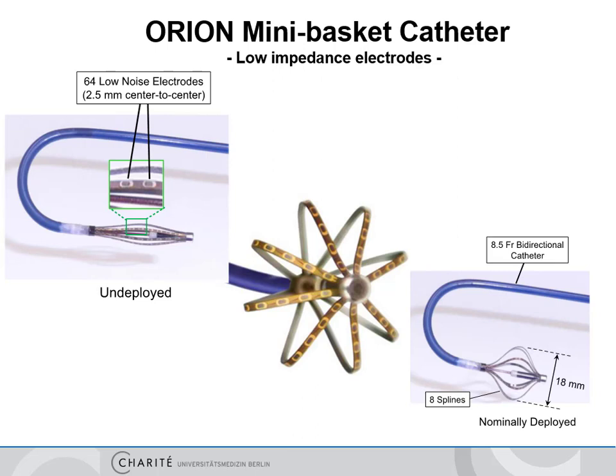So the first tool I'd like to present is the Orion mini basket catheter. It's a catheter with four splines, eight splines, and on all eight of these splines there are low impedance mini electrodes attached. This is different than the catheters we know - the other catheters have electrodes, but these are attached directly, so we have less noise. It's a catheter you can deploy or undeploy and work with. The mini electrodes have only a diameter of 0.4 millimeters. The good thing is you can work with this using a magnet sensor or with impedance. Because of the low impedance, it's not so prone to shifts, so it works better with a magnetic system.